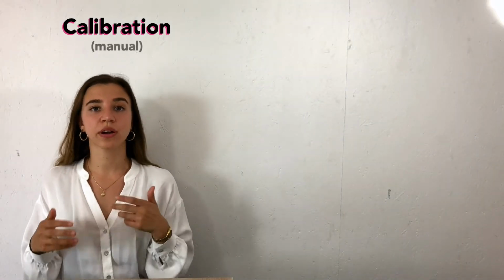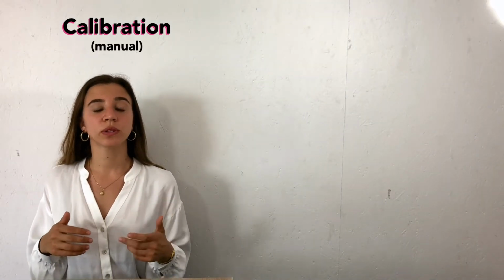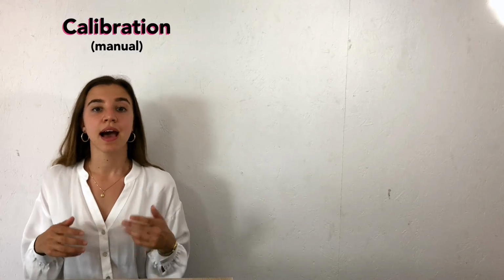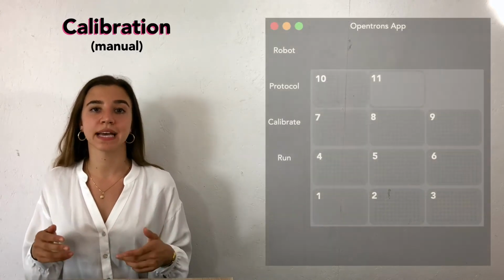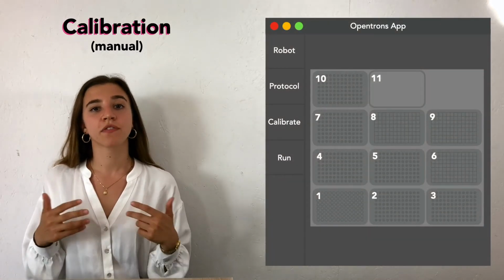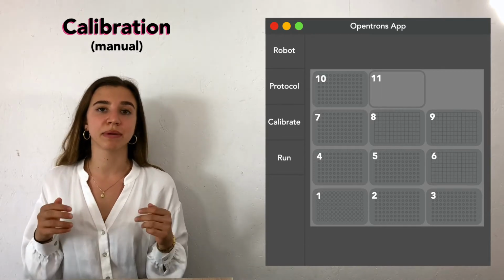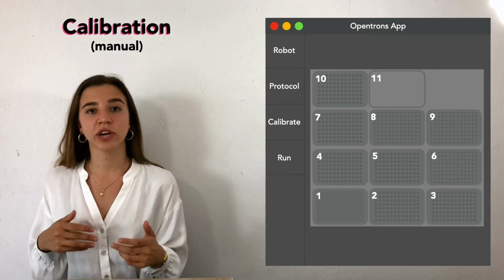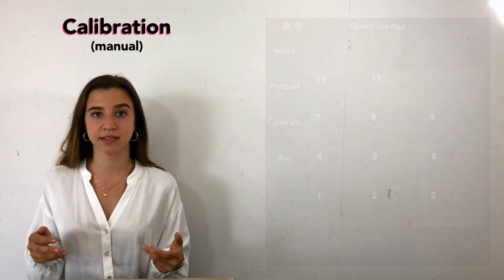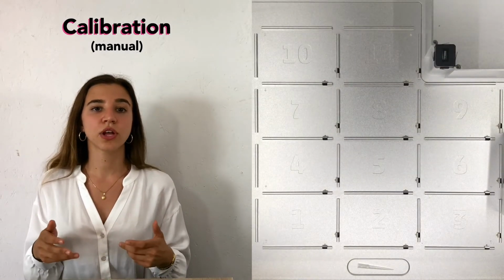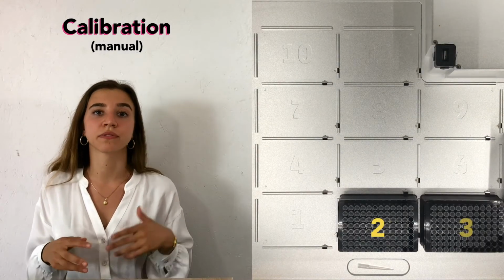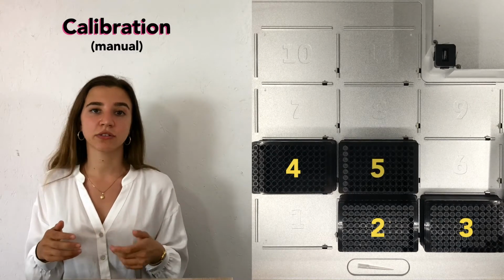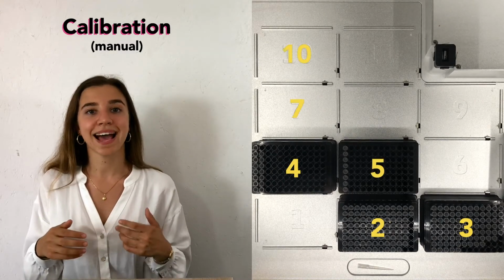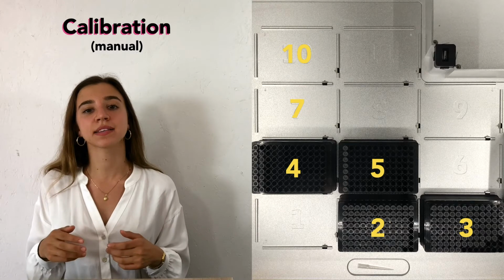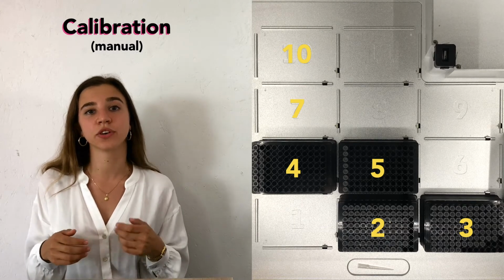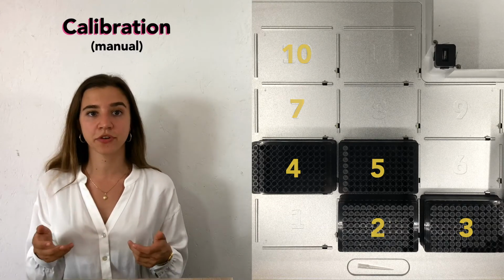To start the manual calibration of the labware, you will need to set up the OT-2 deck as instructed by a virtual deck in the OpenTrons app. Preferably, this can be done with dummy tips and plates to avoid contamination of fresh plastics. Out of the 11 deck slots available, slots 2 to 5 will be used for tip racks. However, depending on the sample number, slots 7 and 10 can also be used for tip racks. This will be detailed by the virtual deck in the OpenTrons app for you.